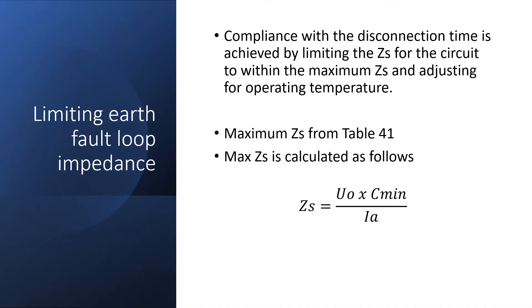To comply with the disconnection time we need to limit the impedance of the circuit to within the maximum ZS from table 41 in BS 7671. The maximum ZS is calculated as follows: ZS is equal to UO multiplied by Cmin divided by IA.